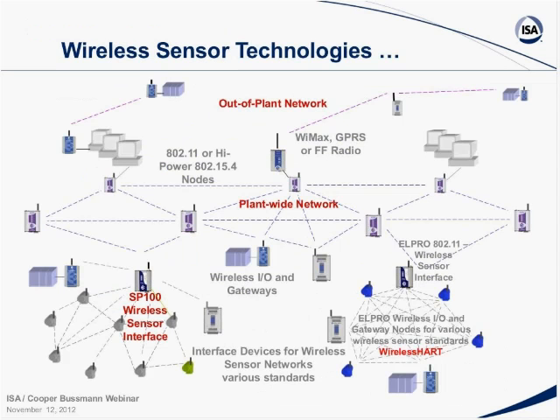When you put it all together, in the lower left we have an SP100 sensor interface with a gateway connecting it in. On the right we might have wired or WirelessHART interfaces coming back in, with our 802.11 network in the center. For longer distances, we might use WiMAX or GPRS radios, or licensed fixed-frequency radios, for example out to a well site tied into a gas plant, or a longer distance out to a tanker along a wharf.